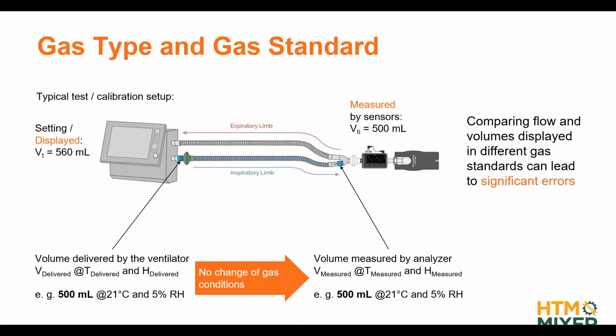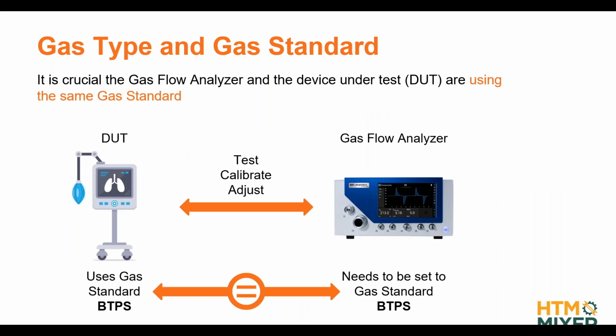So comparing, as you can see now on the slide here, comparing flow rates or volumes in different gas standards can lead to significant errors in your measurements. So how do we tackle that in gas flow analyzers? Well, that's why we have different gas standards we can set up on our gas flow analyzers. And the only thing you need to remember from all that is that your gas standard of your analyzer must match the gas standard used by your device under test.